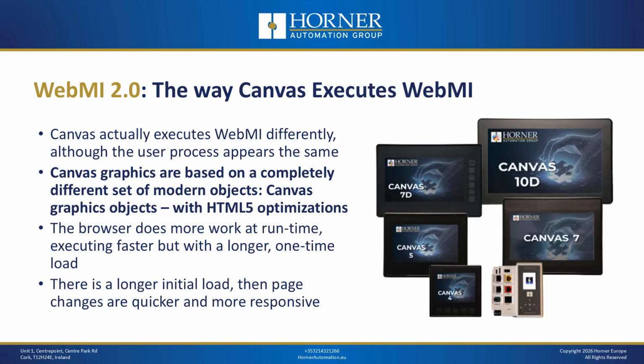WebMI 2.0 is the new and improved version of that process. One of the key factors that initiated the development of WebMI 2.0 was the introduction of Canvas controllers and Canvas graphics. Canvas graphics are based on a completely different set of modern objects, meaning Canvas graphics objects were created with HTML5 optimizations included. The browser now does more work at the start of runtime, executing faster page transitions, but with a longer one-time initial load. Although Canvas executes WebMI differently, the user process is virtually identical.